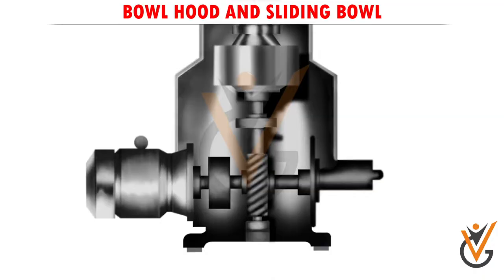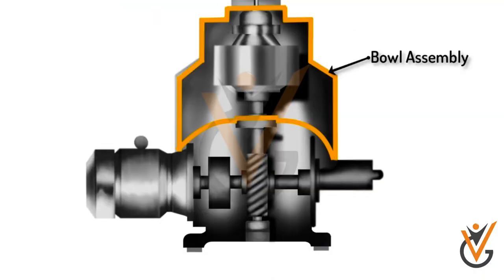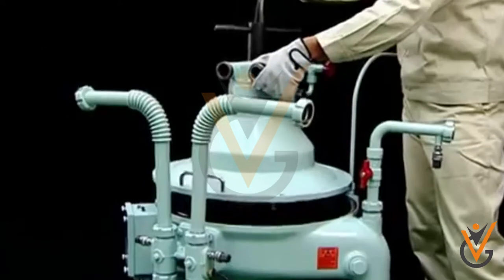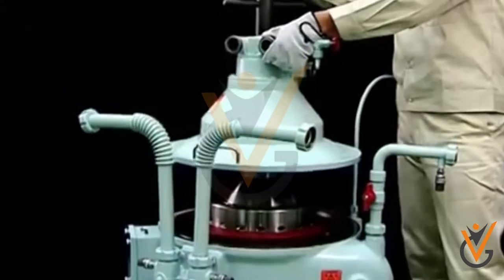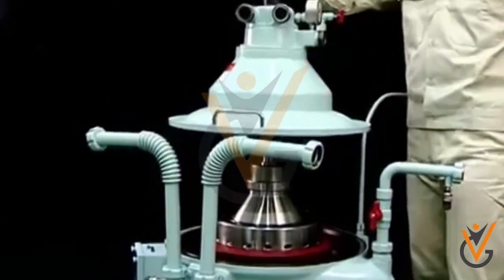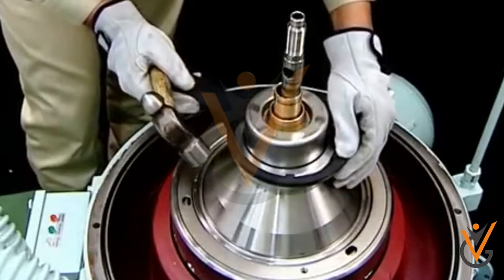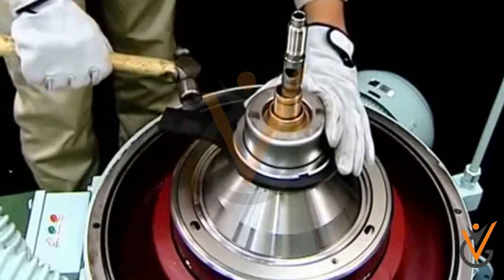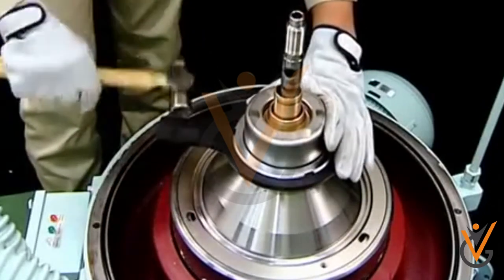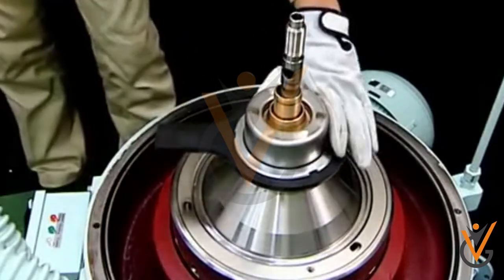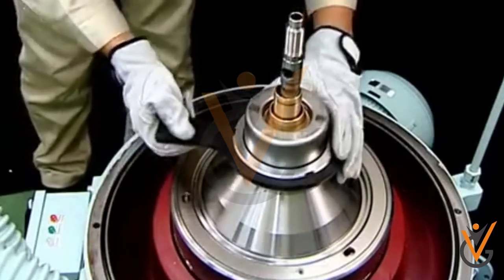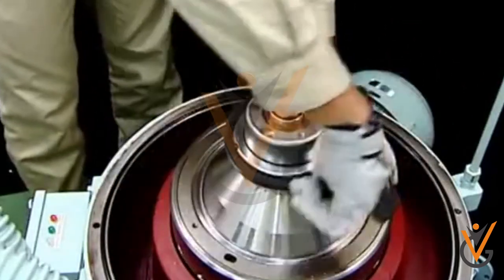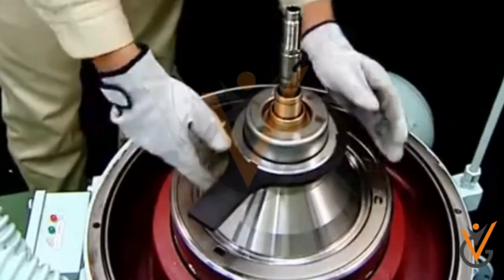Bowl hood and sliding bowl. There are bowls inside the frame, which can be a solid assembly operating non-continuous and have space enough to retain the separated sludge. There can also be an arrangement in which the upper and lower parts are separated for discharging the accumulated sludge by continuous operation. These parts are normally made up of high-tension stainless steel.